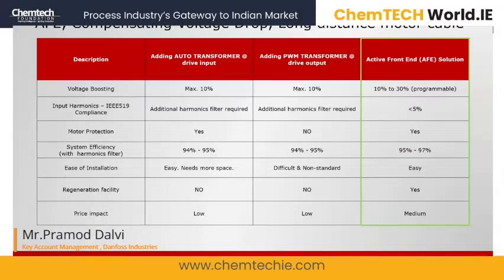And this is the key point which we were discussing before on the voltage drop. So how do active front-end solutions stand out? There are three solutions: we can put an auto transformer at the input to boost the voltage, or we can put a PWM transformer at the drive output to boost the voltage. And third is the active front end, which we have used in this case story. The limitation of the other two is that you can only boost up to 10%, whereas with AFE you can go up to 30%. And for both of the other solutions, an additional passive filter is required, and if you add that, then your efficiency goes down.